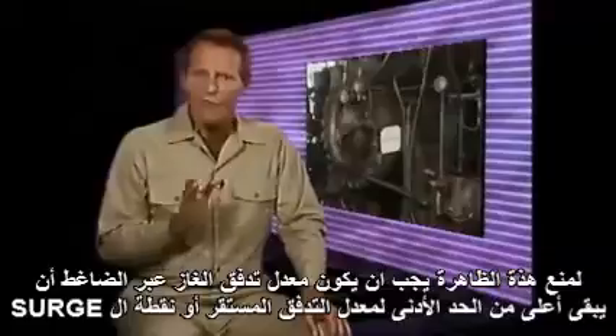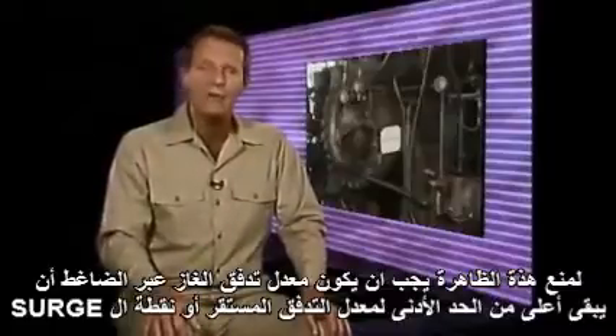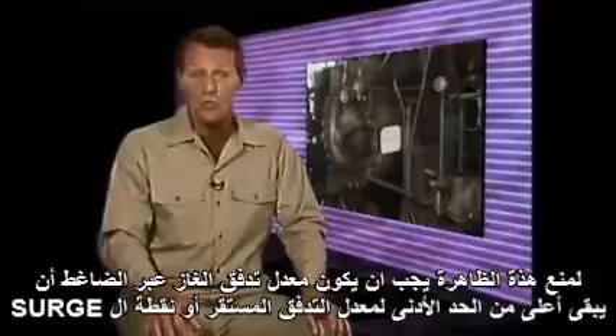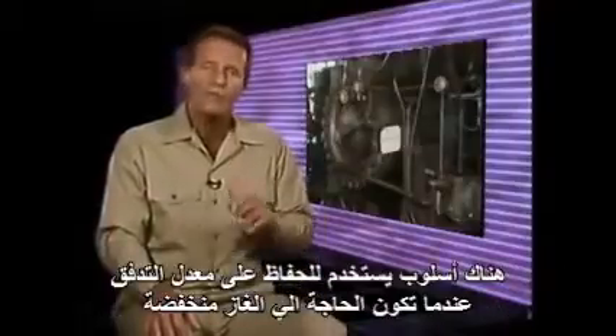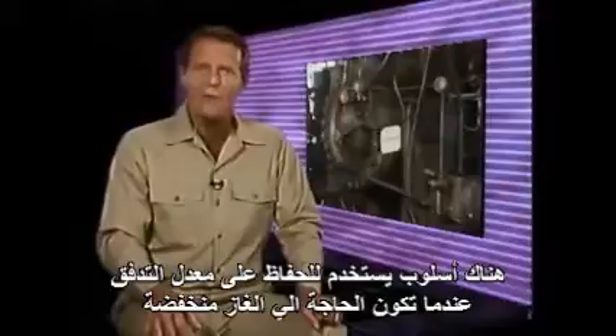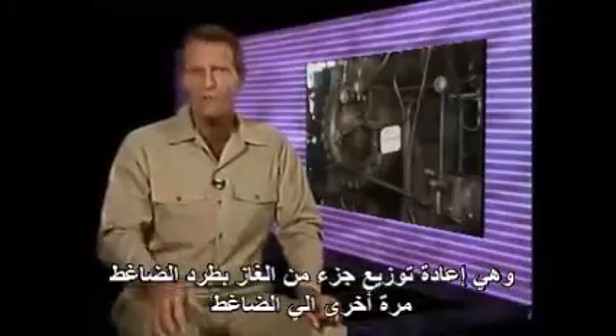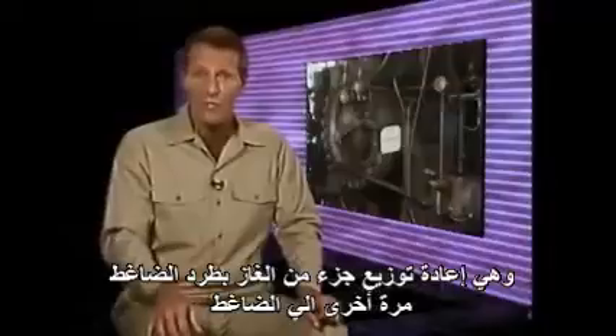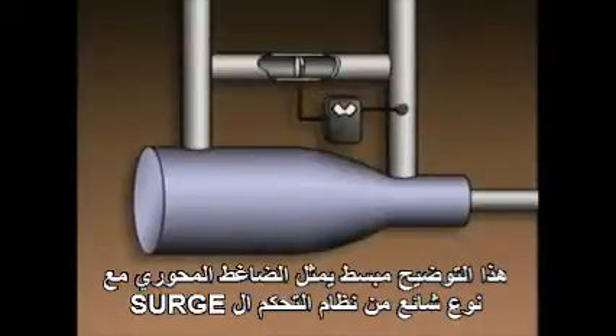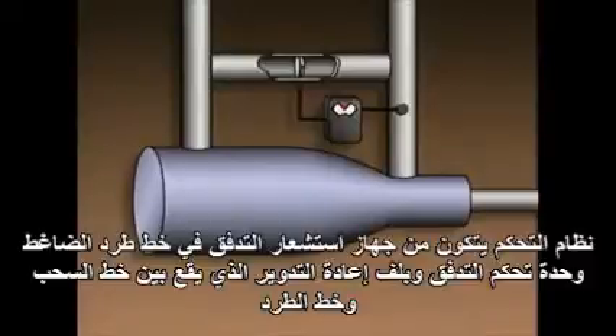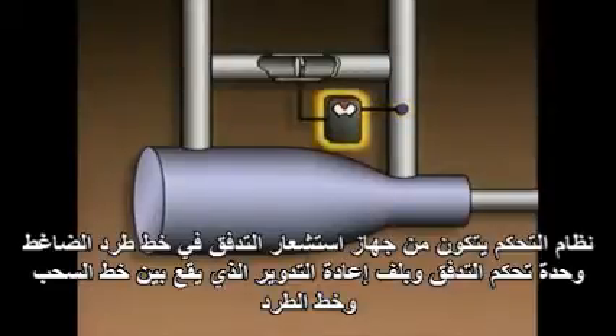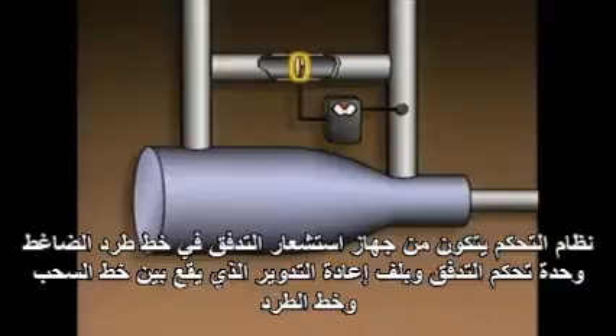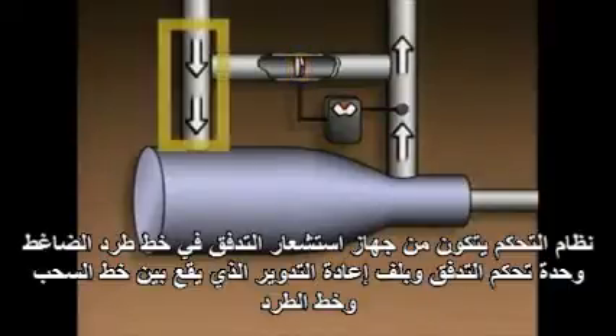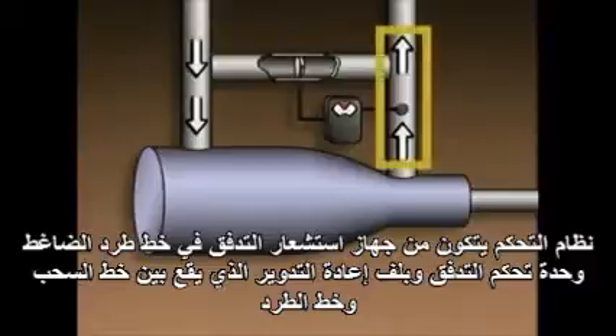To prevent surging, the flow rate of gas through the compressor must be kept above the minimum stable flow rate, or surge point, as it's commonly called. One method that is used to maintain this flow rate when the demand is low is to recirculate a portion of the compressor's discharge back through the compressor. This simplified illustration represents an axial compressor with a common type of surge control system. The control system consists of a flow sensor in the compressor's discharge piping, a flow controller, and a recirculation valve that's located in a section of piping between the suction piping and the discharge piping.